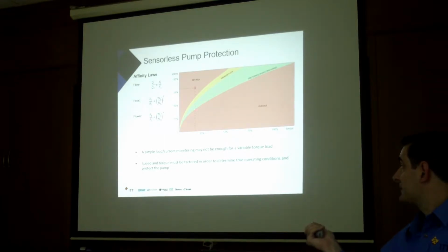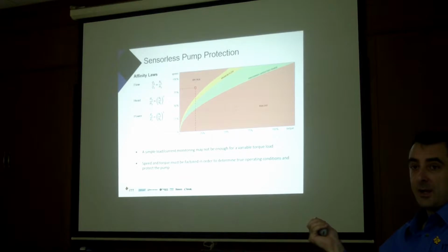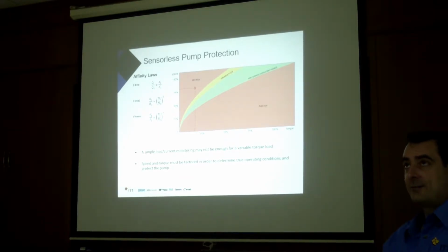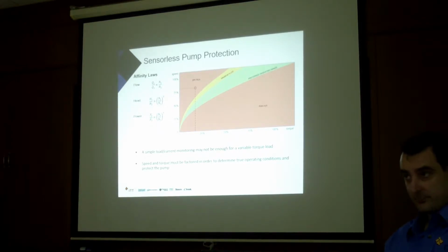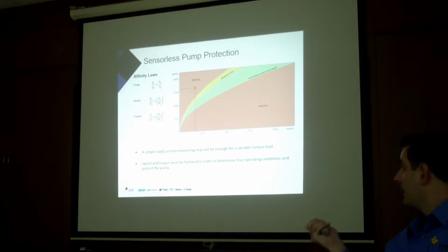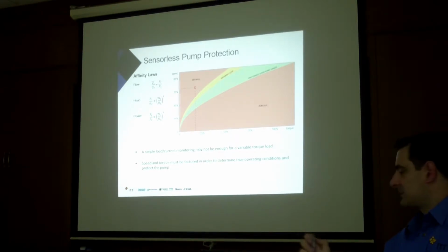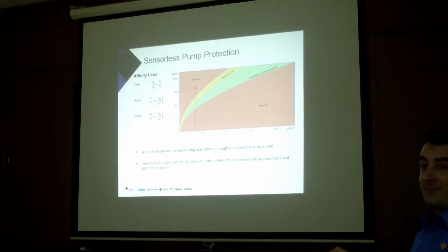So the other big thing is our pump protections. Again, we have a few examples where customers have used a normal variable speed drive to try and, maybe that pump says it's got dry run protection or something, but it doesn't actually work. And the reason a lot of the times is a regular variable speed drive may look at current or torque. ITT considers the pump curve, and we look at current, speed and torque all at the same time.